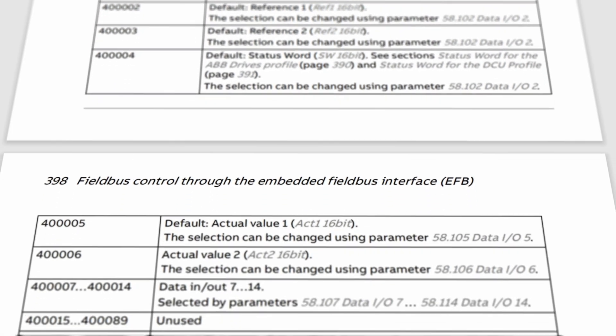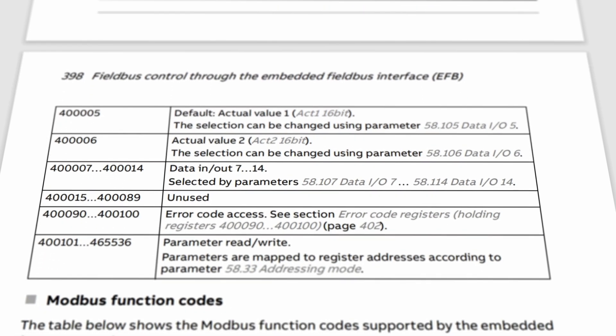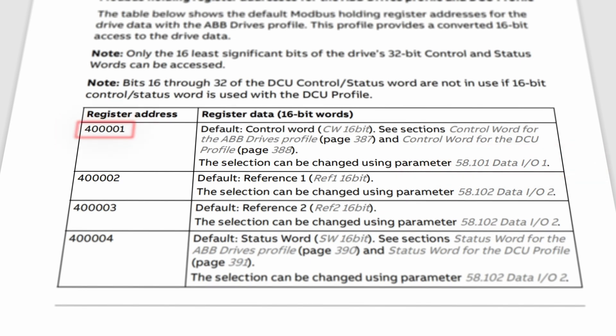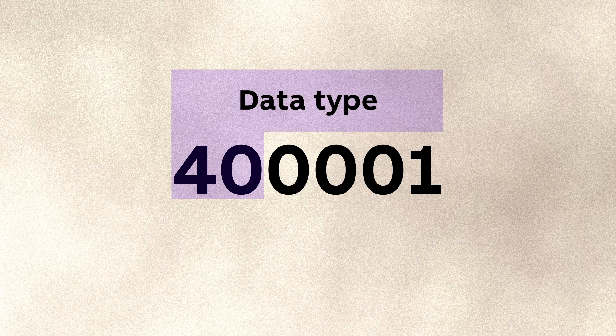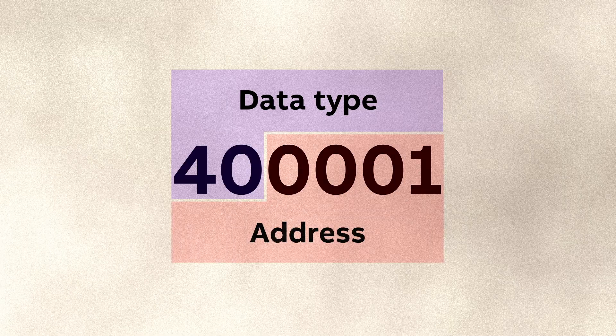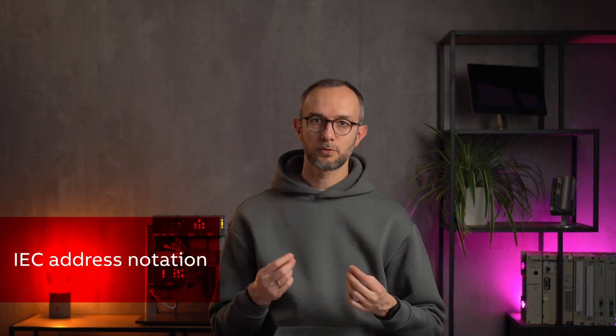One remark on Modbus address notation. While browsing through drive documentation, you will see that the register address is shown in a different way. For example, data IO1 has address 400001 — this is so-called Modicon notation. Technically it is outdated, but many vendors still use it because it incorporates both the data type (4 stands for holding register) and the address. To get the IEC address that the PLC operates with, you need to remove the 400001 part, which leaves us with address 0.